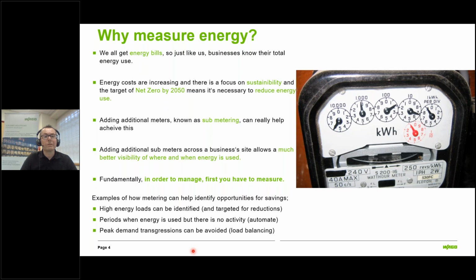Other drivers, such as the net zero targets, are also influencing this behavior. Using a meter or adding additional metering is known as sub-metering, and this can really help achieve this, as we'll see. And it all comes back to the old adage that if you want to manage, first you have to measure. And this can therefore be used to help identify high loads or when energy is being used, but there is no activity. And indeed, you can also, as a business, manage your energy better to avoid peak demand transgressions, which can result in high costs.